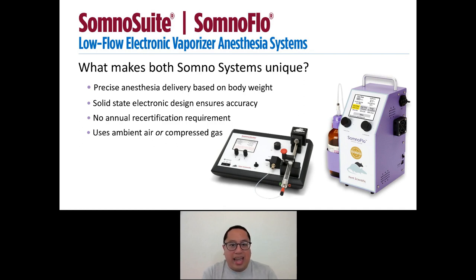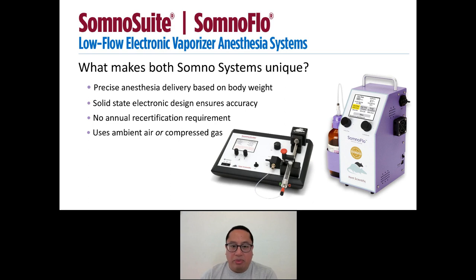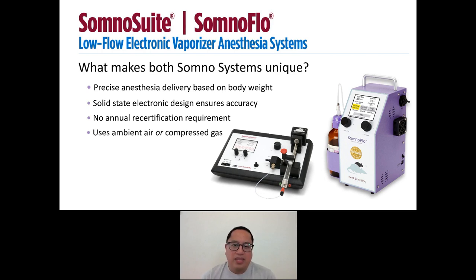Both the SomnoSuite and SomnoFlo low flow electronic vaporizer systems provide advantages over traditional high flow vaporizers. Anesthetic concentration and flow rate delivery is based on the animal's weight. Traditional canister style vaporizers contain wicks, dials, and other moving parts that need to be calibrated or recertified to maintain accuracy. Both the SomnoSuite and SomnoFlo use solid state electronics to ensure accuracy and do not require annual recertification. This precise delivery ensures both animal and user safety.